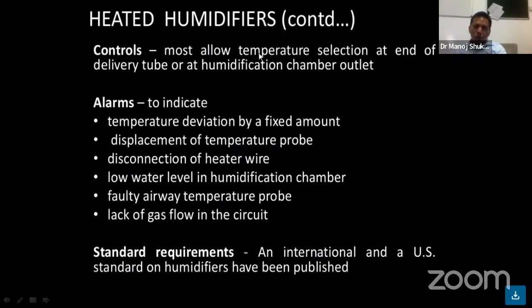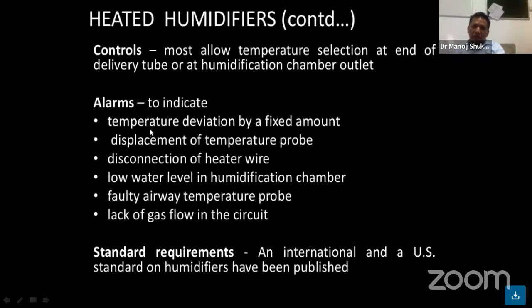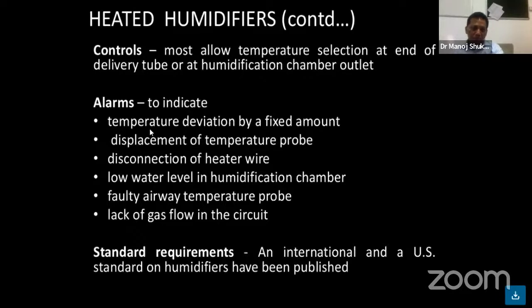Controls allow for temperature selection at the end of the delivery tube at the humidification outlet. There is a set of alarms which indicates temperature deviation by a fixed amount, displacement of the temperature probe, disconnection of heat wires, low water level in the humidification chamber, and lack of gas flow.